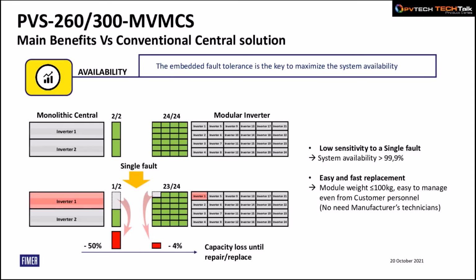As far as availability is concerned, today typically a 7 megawatt skid is composed of two central inverters, while with our solution we have 24 independent inverters running to generate the same amount of power. The difference is evident when a single fault happens. With the central inverter, you have 50% of the system offline, so you lose 50% of the capacity, while a module offline will generate just 4% of capacity loss. So low sensitivity to a single fault is one of the key attributes of this solution, and is enabling us to enhance the availability above 99.9%.